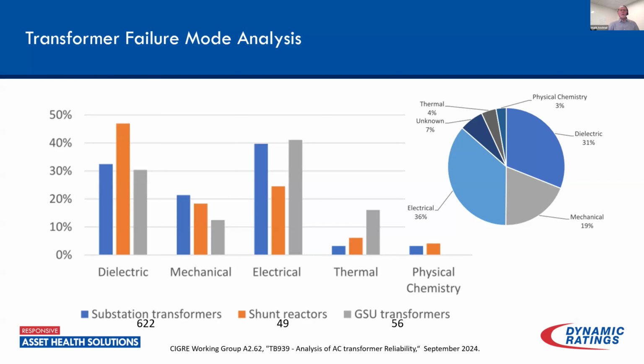So when we break this apart a little bit, traditional substation transformers and GSUs are pretty much the same. Now, again, unfortunately, our renewables are mixed up in here. For generator step-ups in renewable applications, I think most industry experts really believe that we're seeing increased failure modes. But unfortunately, there just hasn't been enough of a focus on people reporting that, hey, this was in a renewable application, and maybe we need to treat this separately or categorize it differently. But ignoring shunt reactors, you can see both the substation transformers as well as the GSU transformers basically have similar failure modes. Dielectric is a big issue. Electrical is going to be a big issue, and I'm going to cover what we expect to happen as we introduce more renewables and how these failure modes might change.